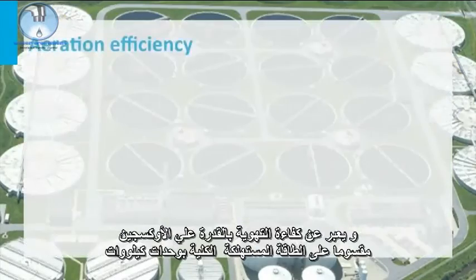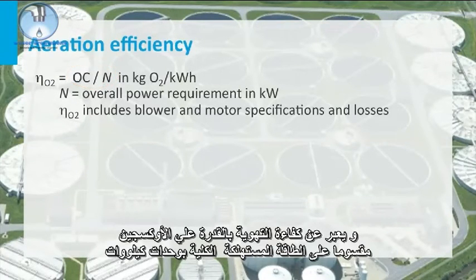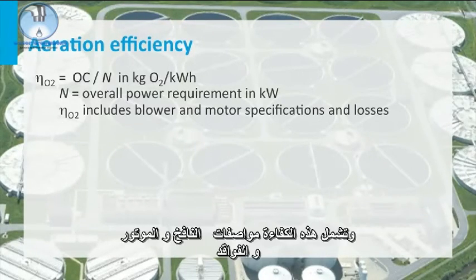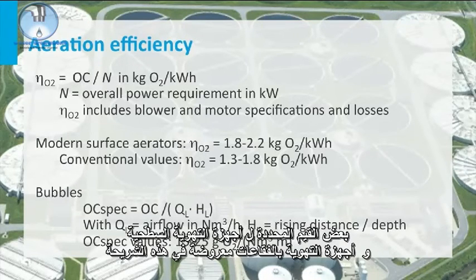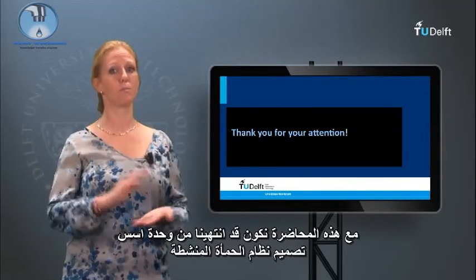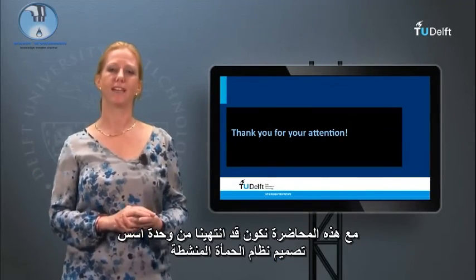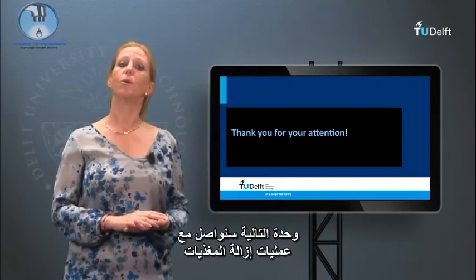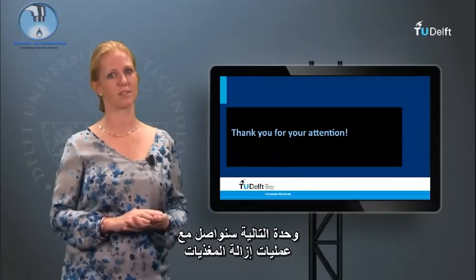Aeration efficiency is expressed as the oxygenation capacity divided by the overall power requirement in kilowatts. This efficiency includes blower and motor specifications and losses. Some specific values for surface aerators and bubble aerators are given in this slide. The efficiency of bubble aerators highly depends on the rising distance or depth of the tank. With this lecture, we close the module on basics of the design of an activated sludge system. Next module, we will continue with the nutrient removal processes. See you then!